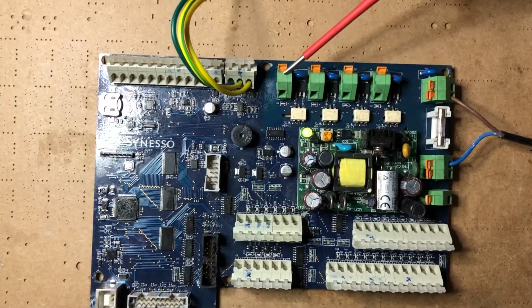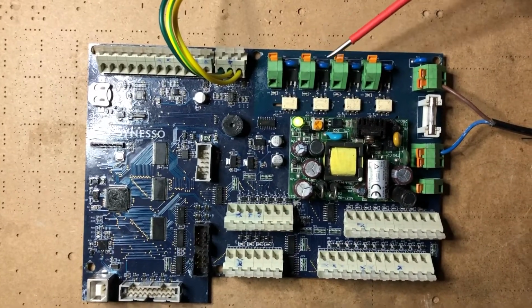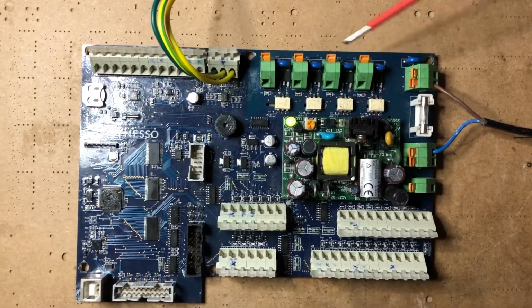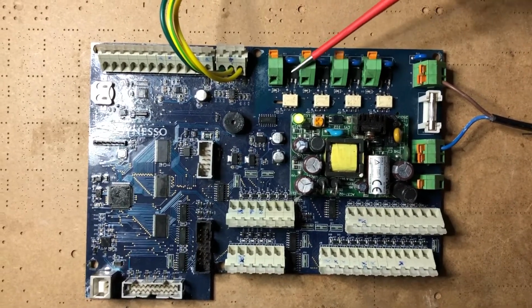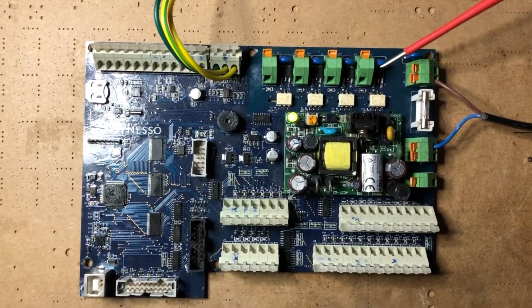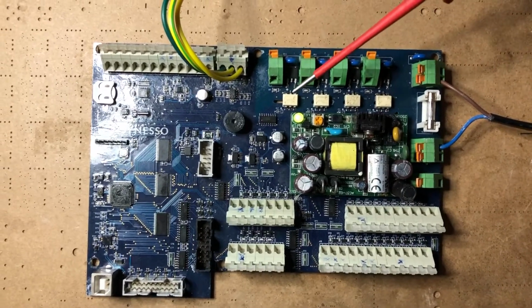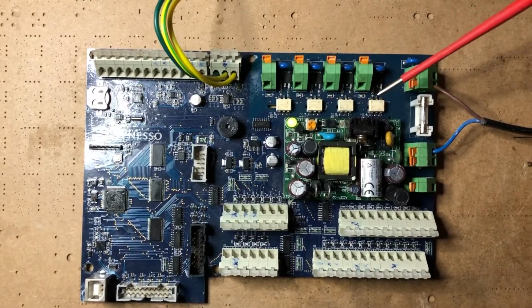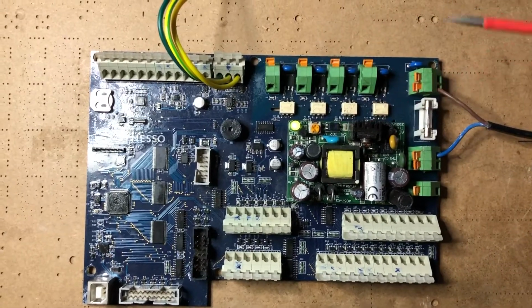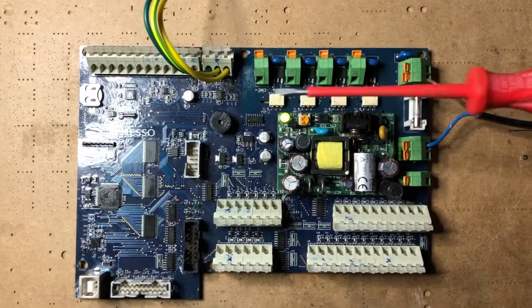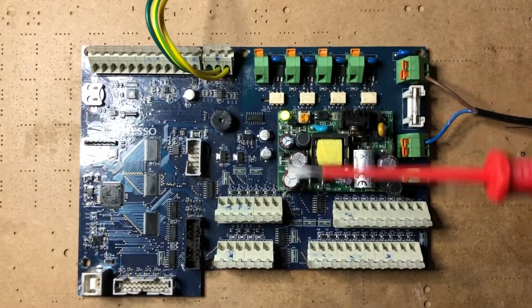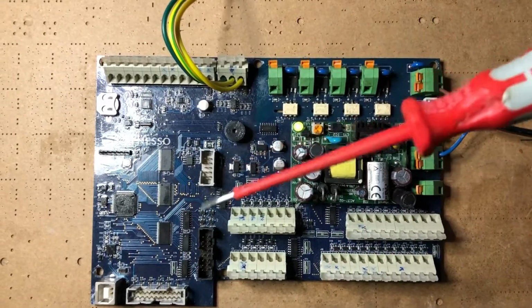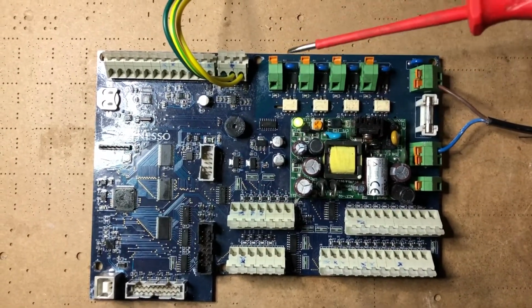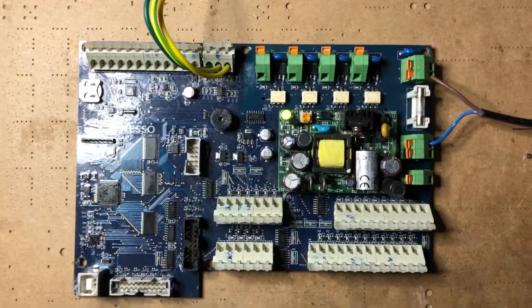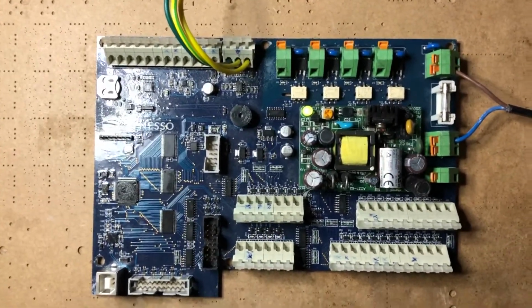So here we have group 1 pump output, group 2 pump output, group 3 and group 4, left to right - 1, 2, 3, 4. These are simply switched by a triac, 1, 2, 3, 4 triacs, and they are in turn switched by an optoisolator, so optically isolated and separated within a range of about 3,500 volts protection between the high side and low side electronics. So the CPU switches the optos, the optos switch the triacs, the triacs switch the pumps.